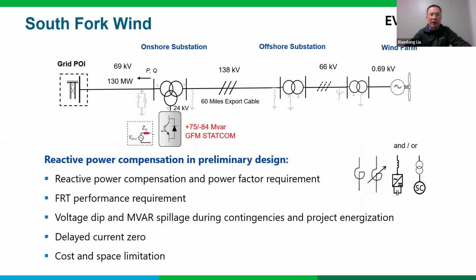All right, so this is a simplified one line of South Fork Wind, which connects to a Long Island 69 kV network with 130 megawatt generation. The export cable here is 138 kV, 60 miles long, and it connects to the secondary side of a 3 winding transformer. The STATCOM right here is connected to the 24 kV tertiary of the 3 winding transformer. The STATCOM is basically plus or minus 75 Mvar with overloading capacity up to 84 Mvar for 3 seconds in inductive mode.